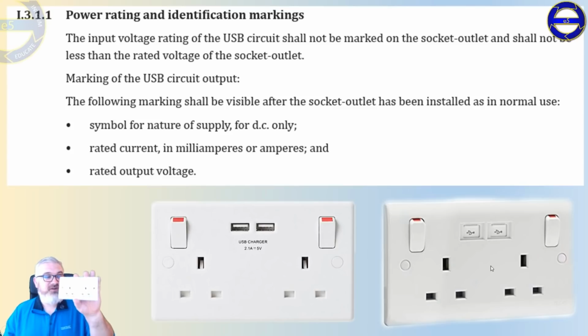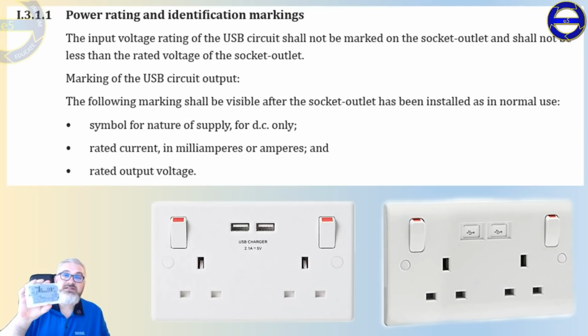Now, if I go back to this device, which is the Eaton one, it's actually pretty well built, but the Eaton one doesn't comply, and yet on the back it clearly states it's compliant with BS 1363. So I am as miffed as you watching this. But what it does tell us is different manufacturers have different ways of complying with the intent of the standards, or possibly they're not up to date with the current requirements of the standards. So it's worthwhile asking the question of your manufacturers or of your wholesalers and the people that provide you with the devices, just if anything to make sure you're future proof. As we saw, the device here on the left as of 2020 won't be compliant with the low voltage directive.